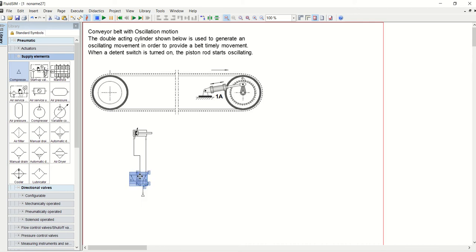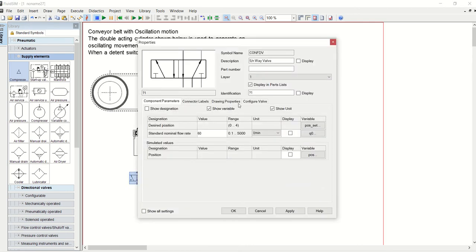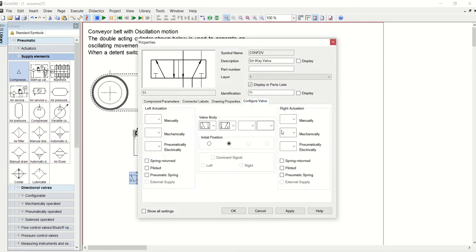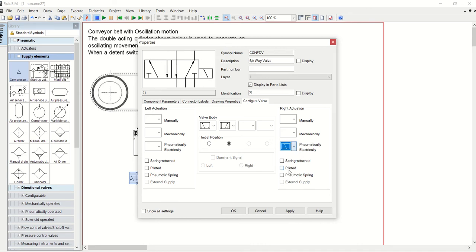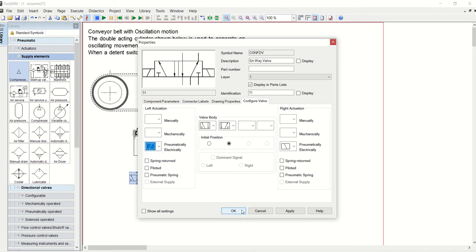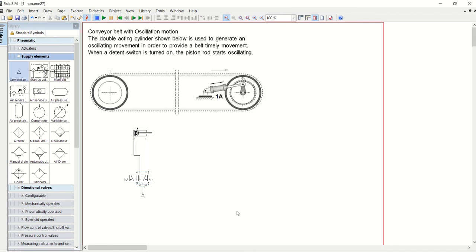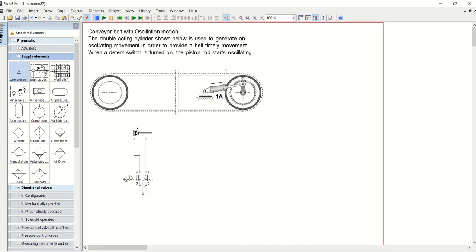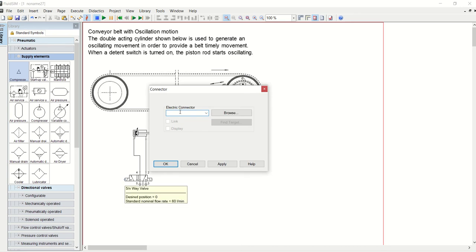Now let's configure the 5/2 valve. We go to configure valve, and then on the right hand side come down to pneumatically operated and electric, pick electric which is the solenoid, and then on the left hand side do the same. We have to label these solenoids with the designated names given to it, so we will give it Y1.